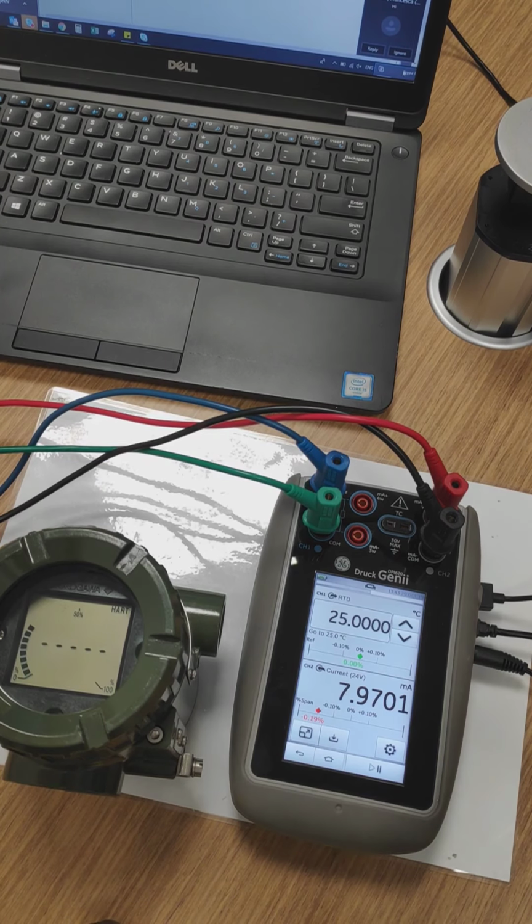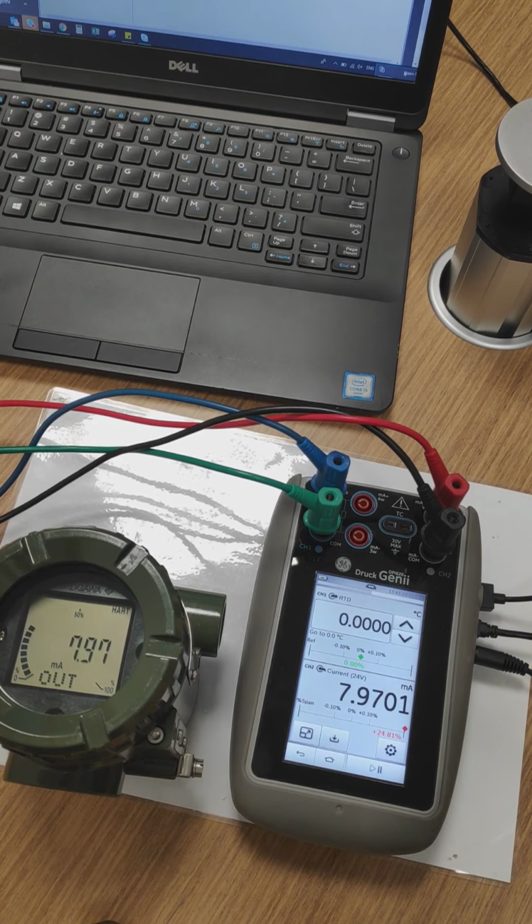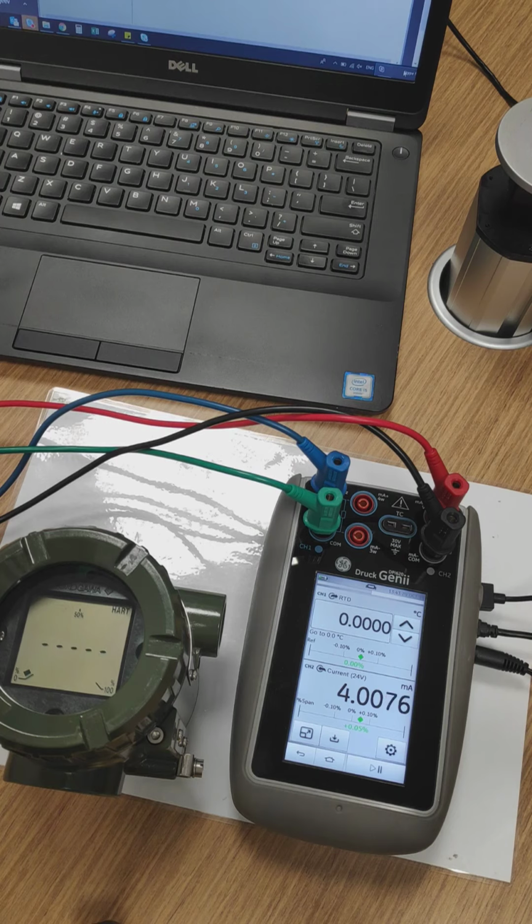Okay, stable. Next point at 0 degrees. Then, as we wait, it's going to green, which means that the 0 point is fine, and this gives an early indication that we need to look at either a trim or a span or full scale adjustment, which I believe is the case.